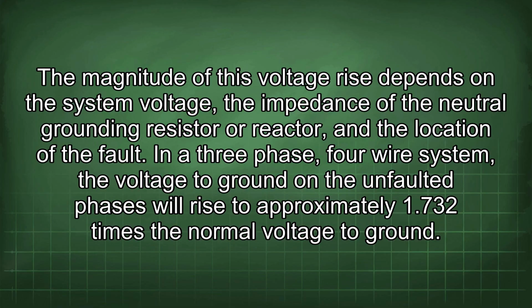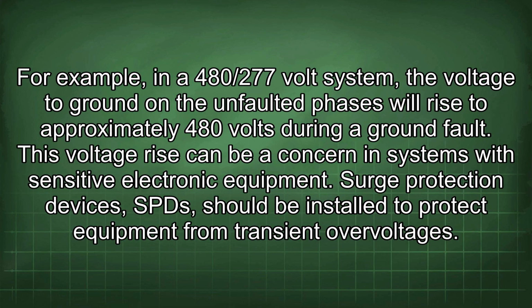In a three-phase, 4-wire system, the voltage to ground on the unfaulted phases will rise to approximately 1.732 times the normal voltage to ground. For example, in a 480/277 volt system, the voltage to ground on the unfaulted phases will rise to approximately 480 volts during a ground fault. This voltage rise can be a concern in systems with sensitive electronic equipment.